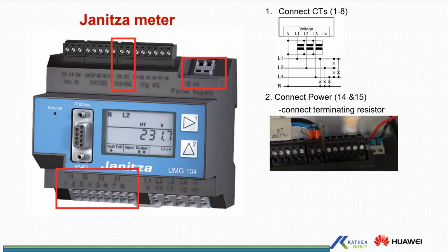One thing to note when connecting power meters, make sure that your voltage and current are in line. If there is a phase difference between the current and the voltage, the power ratings that will be calculated by the algorithm will be wrong. So make sure that if your CT is hooked up on L1, that CT is wired on I1, and the line voltage from that phase is wired on L1. If you have a mismatch, then you'd have wrong values. Mainly, this is depicted by a low power factor or a negative power factor or a high reactive power. So make sure that your current and voltage are in phase whenever you wire power meters.